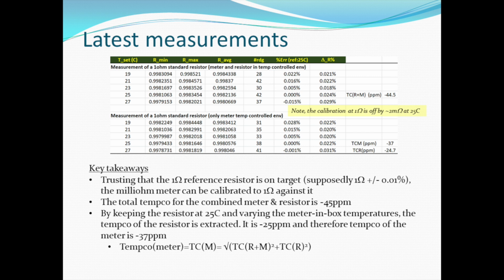Okay, so this is the measurement of the 1 ohm standard. This is fairly detailed results over here, and we have 2 cases, one where I have the 1 ohm standard resistor and the meter in a temperature control environment. And the leftmost column is your temperature in Celsius from 19 to 27 degrees Celsius. Then you have the R min, R max, R average, coming out of the meter, the HP 34401A, and then the number of readings I took at each of these temperatures, and then an error calculated based on 25 degrees Celsius being a 0 error.